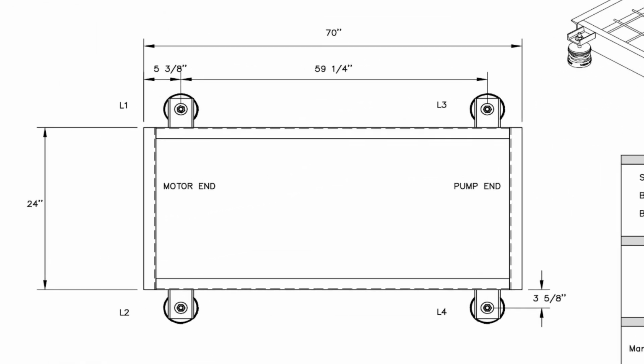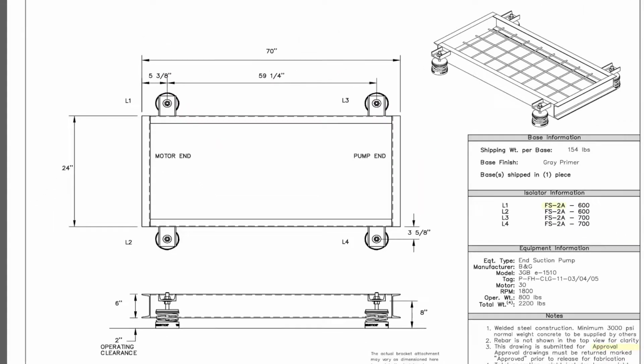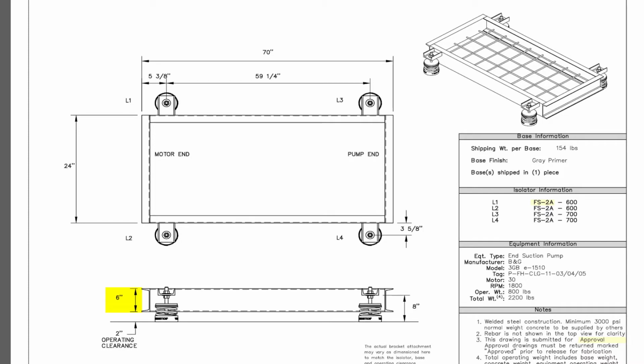I'll take a moment here to highlight a rule of thumb design attribute. Note that the distance between the isolators here is 59¼ inches. A typical parameter used in inertia-based design is that this distance should not exceed 10 times the base depth, and since this is a 6-inch deep base, we meet that. In some cases with larger equipment, it can be better to increase the depth of the base to minimize the number of isolators required.